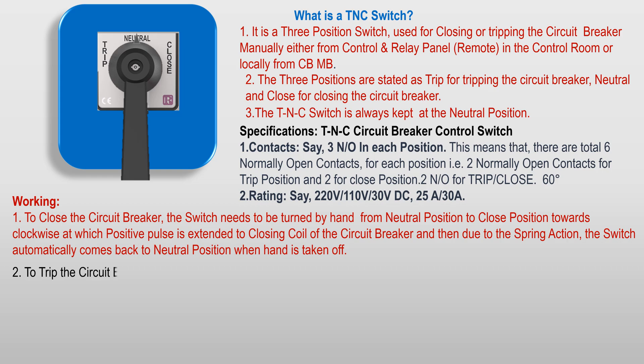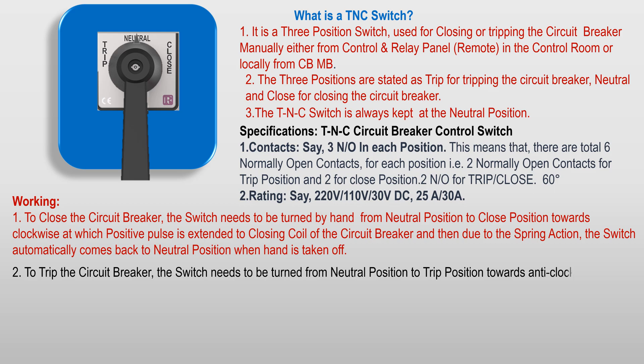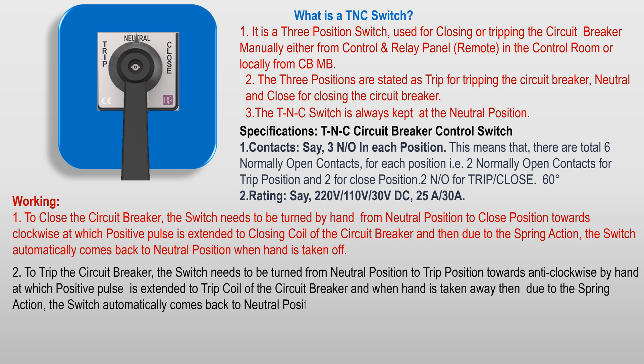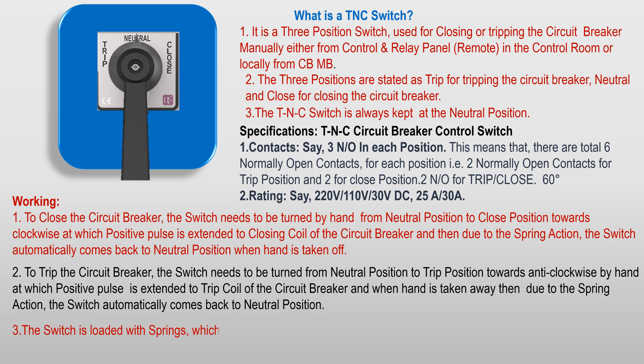To trip the circuit breaker, the switch needs to be turned from neutral position to trip position in the anticlockwise direction by hand, at which a positive pulse is sent to the trip coil of the circuit breaker. When the hand is taken away, due to spring action, the switch automatically comes back to the neutral position. The switch is loaded with springs, which ensures that it returns to the neutral end position after any operation — close or trip. This is done to send a positive pulse to the closing or tripping coils for only a short time.